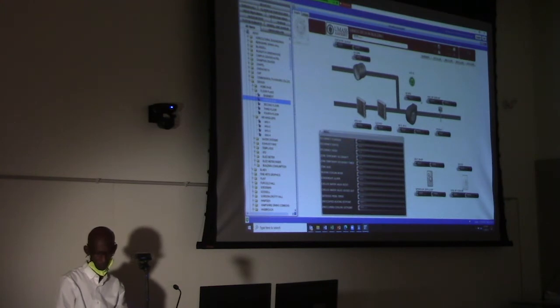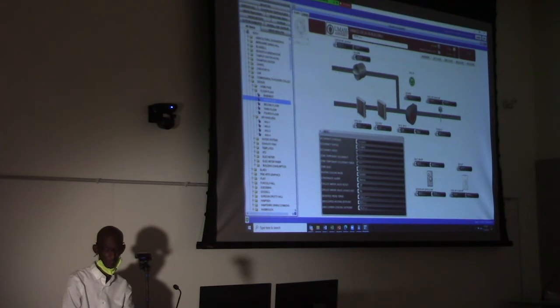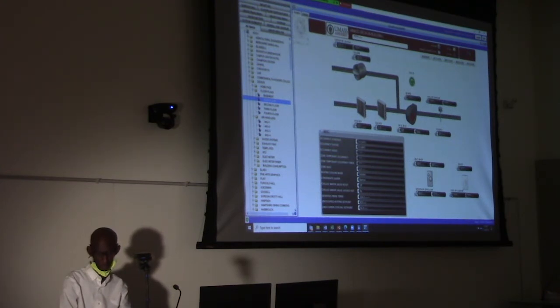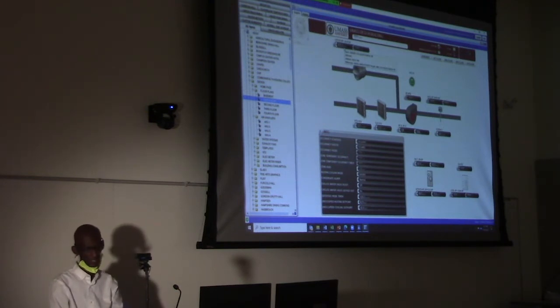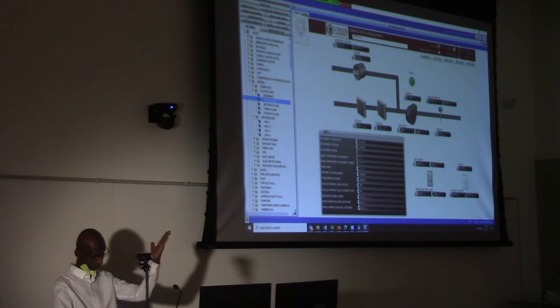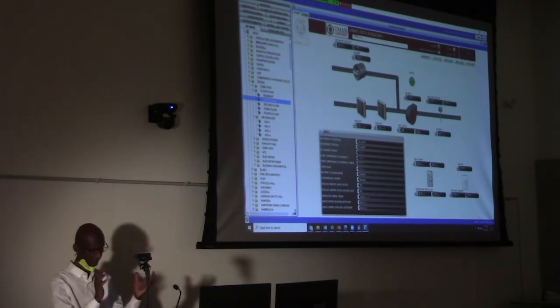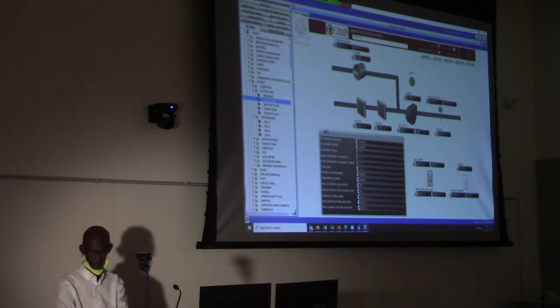So sometimes it can be slow. So we have outside air coming in. We have the damper that's open 100%. It's supposed to supply us air here. It's taking time, I hope. So we have the set point here of 625 CFM of outside air. So hopefully it's going to start soon. And then the damper is open 100%, which means it should be supplying the maximum capacity. And then this fan coil unit here, you can see this is supplemental. We have air coming in, but this one here kicks in only for heating or cooling. So if, for instance, the thermostat we have here, which is set to 68, you see? You see the thermostat at 68?